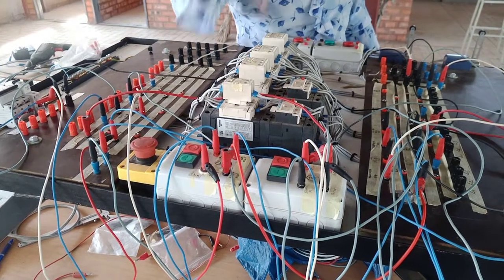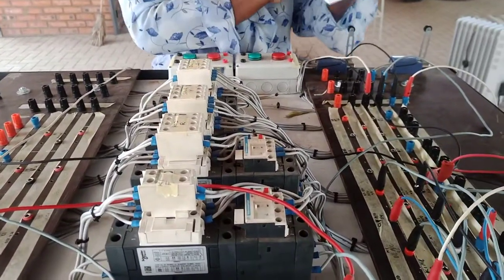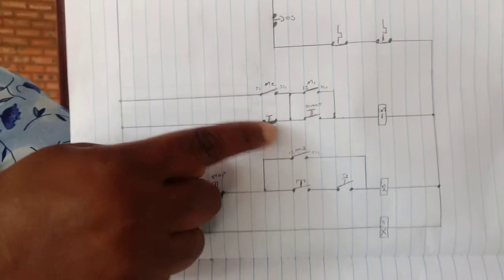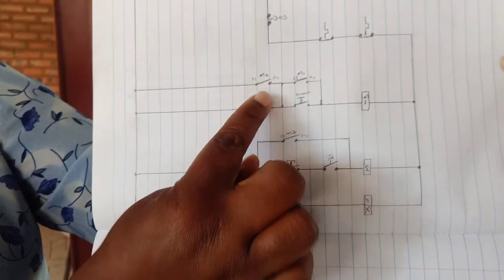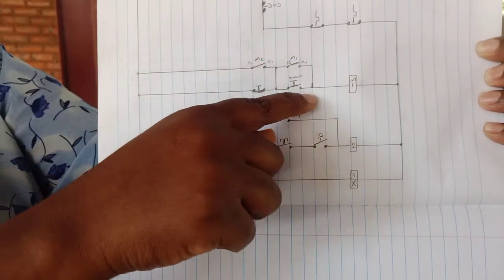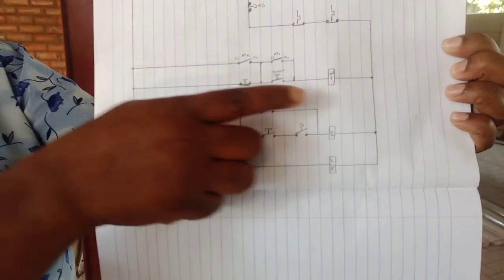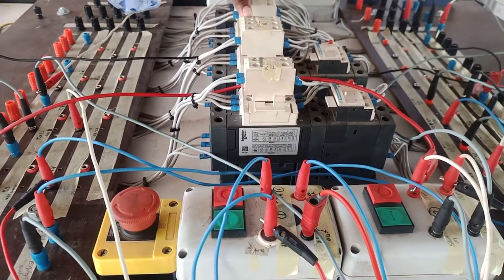Let me show you why. You can check here — our M2 normally open contact is connected in parallel with our stop button for Motor 1. So even if I press the stop, because Motor 2 is energized it is closed, providing a parallel current path through this normally open contact. Motor 2's normally open contact effectively short-circuits the stop button for Motor 1. Hence, pressing stop doesn't work — it doesn't stop Motor 1 until Motor 2 is deactivated.